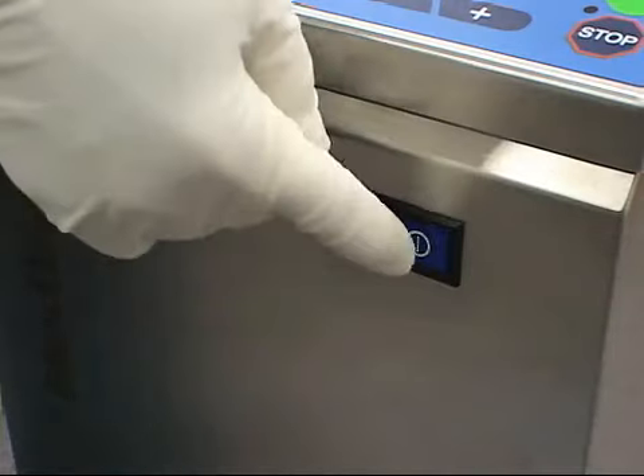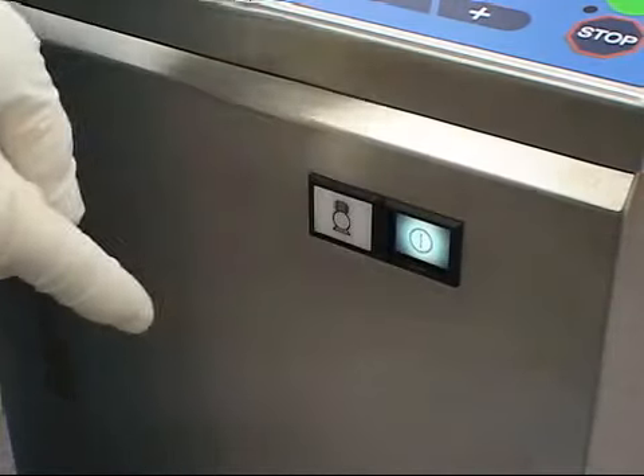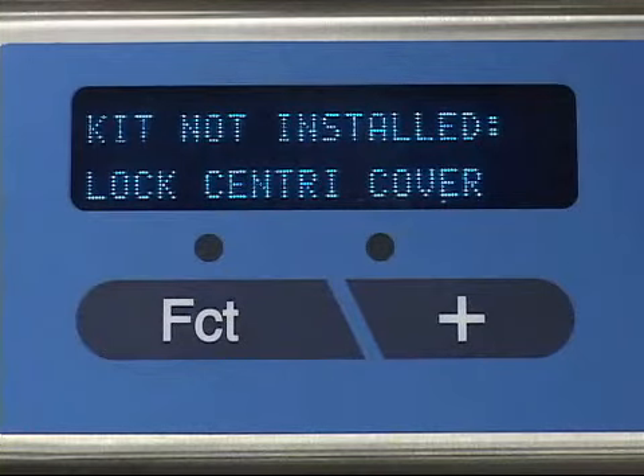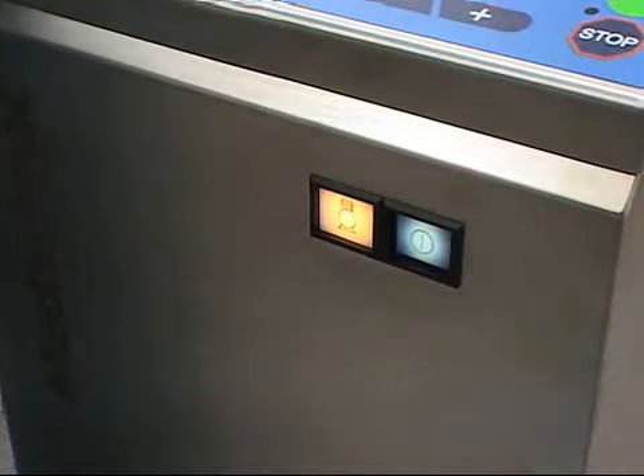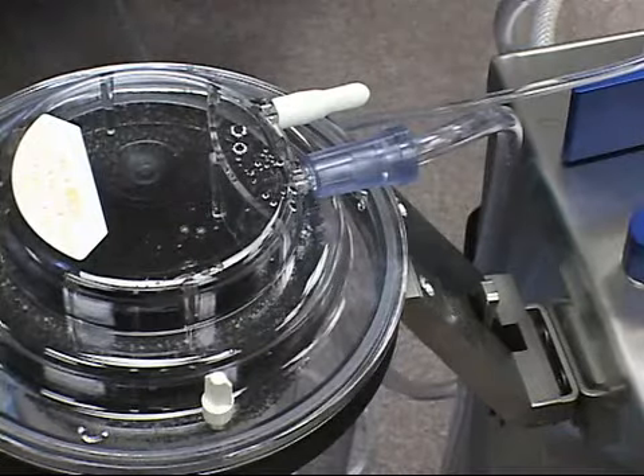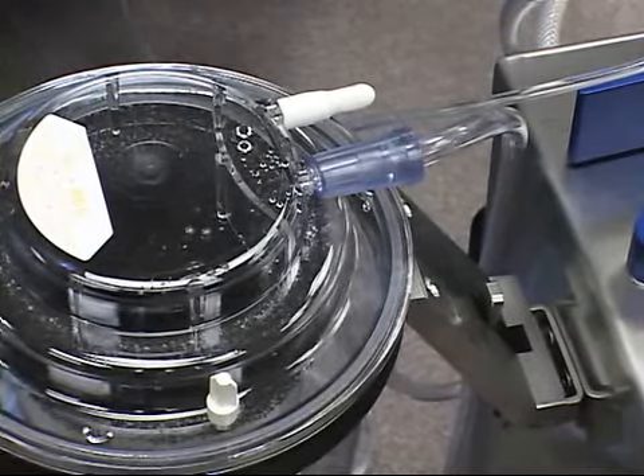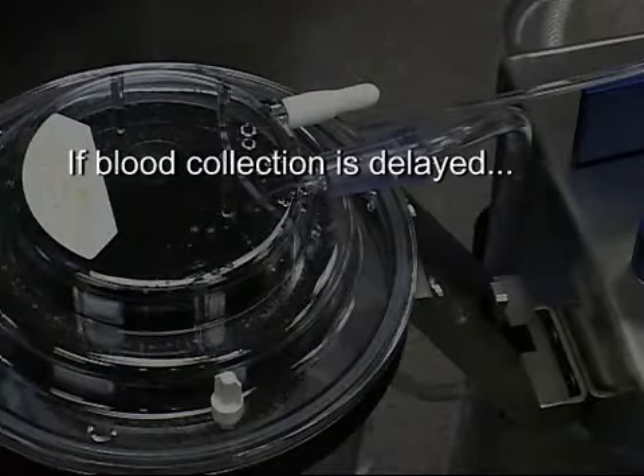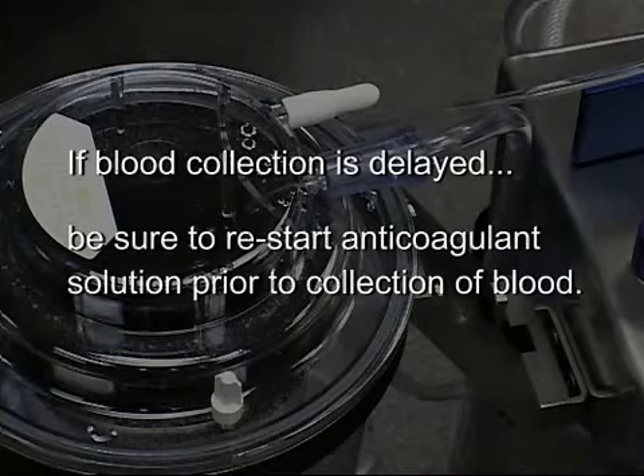Turn AutoLog power on. The machine will display "Kit not installed. Lock centrifuge cover." Blood collection may now begin. If blood collection is not going to start immediately, within 5 to 10 minutes, the anticoagulant flow may be stopped. Be sure to restart the anticoagulant solution prior to the collection of blood.